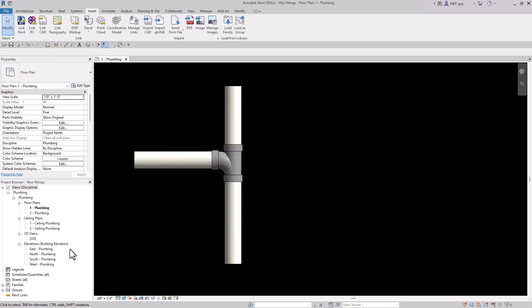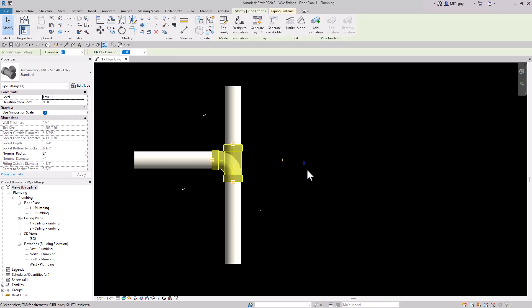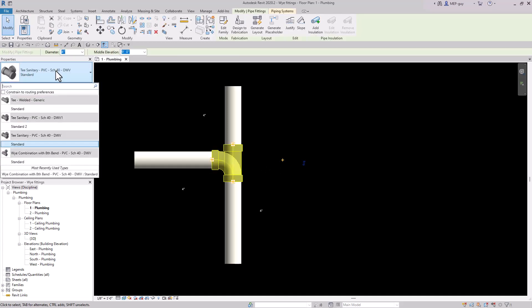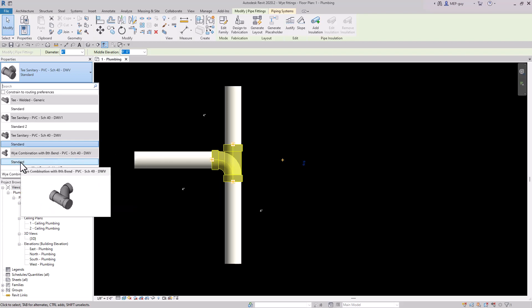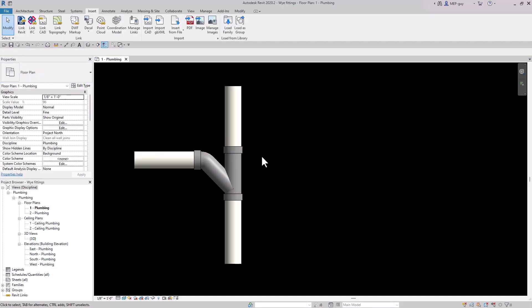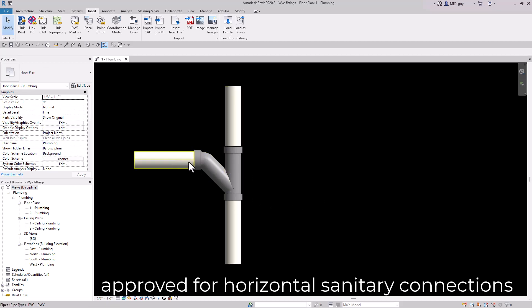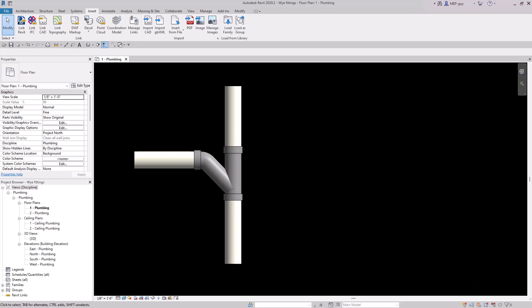Now that the combo fitting is in my project, I can click on the sanitary tee, click the dropdown, and you can see the Y combination is available. I can easily just change that. Now I have a combination Y, which under the International Plumbing Code (IPC) is approved for horizontal sanitary connections. But what if I want a true Y fitting?